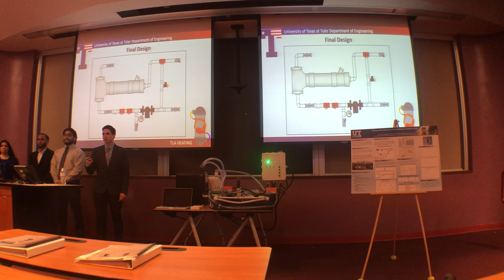When the system is working, two main types of flow are going to occur. One is going through the heat exchanger, when the system is in operation in the lab setting. When we want to reach a certain temperature quicker, we bypass the flow toward the heat exchanger, and we recirculate the flow in order to be able to better control the temperature. When we want to cool down the fluid, one actuator is going to deviate the fluid towards the chiller.